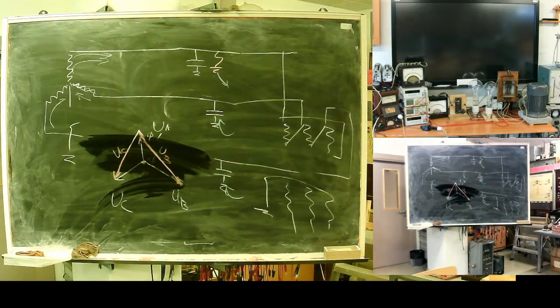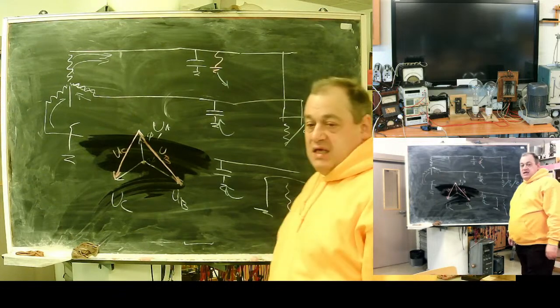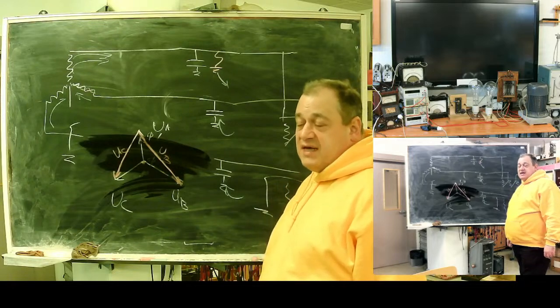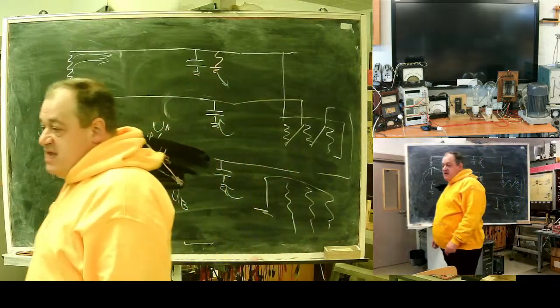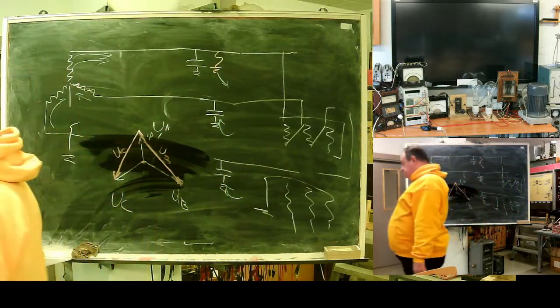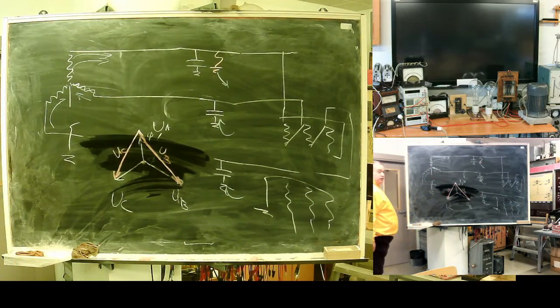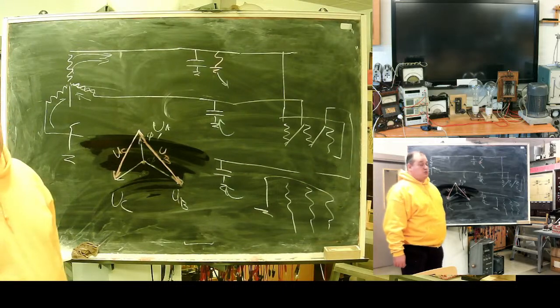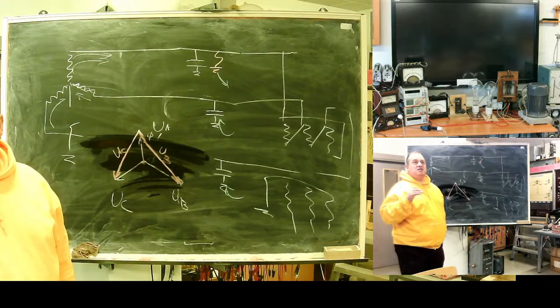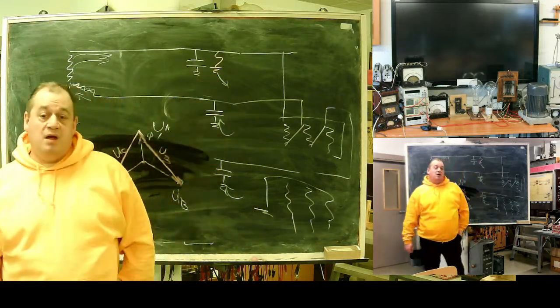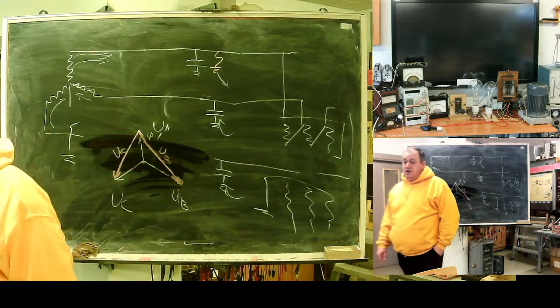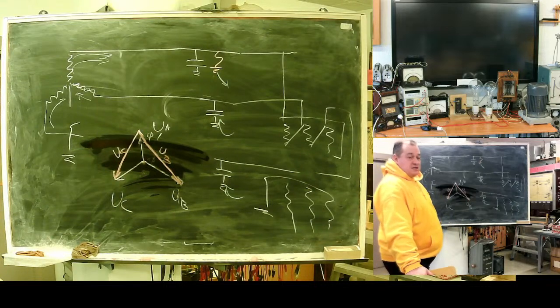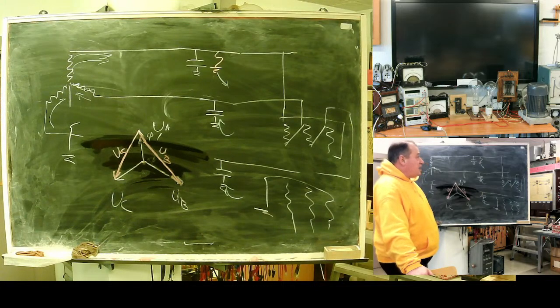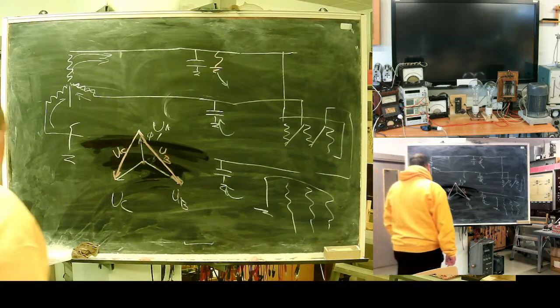Such a network gives us one positive thing. We can continue operation even in case of a ground fault. In general, at first look, there is a limited current at the fault place. Old rules allowed operating 8 hours without doing anything if the current is less than 15 amps. Higher current can damage something, a wire or something like this.